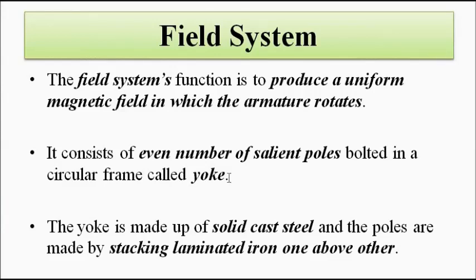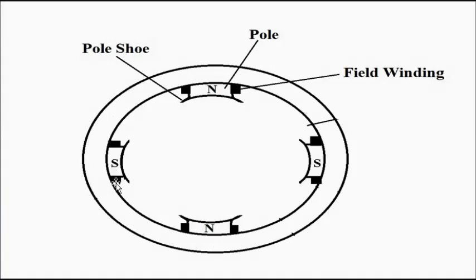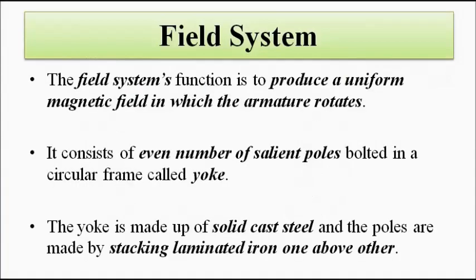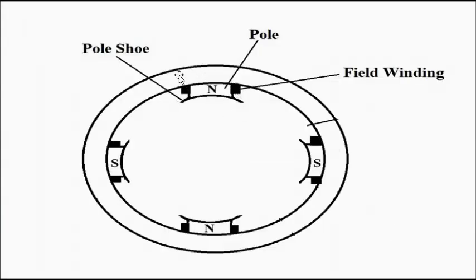In that circular frame we have an even number of poles bolted to it. The field system looks something like this — we have the circular frame called the yoke, and on this frame we have these poles bolted on it. The circular frame yoke is made of solid cast steel, and the poles are made of laminated iron pieces which are stacked one above the other. Around these poles the field windings are wound.